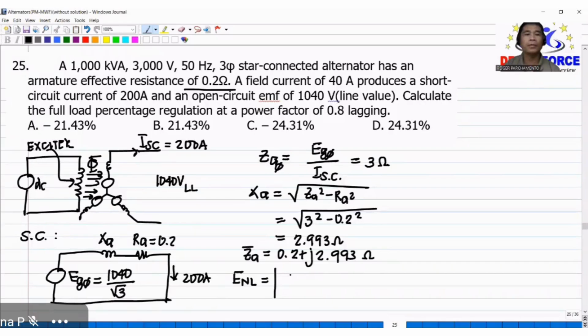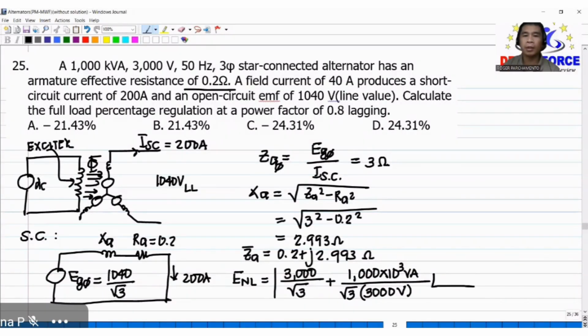E no load, magnitude of the line voltage 3000 volts. Gawin natin siyang per phase, so divided by square root of 3. Then plus yung line current. Line current is the output 1000 kVA, so times 10 to the 3 volt ampere all over square root of 3 times the line to line voltage is 3000. The angle would be a negative arc cosine 0.8. Then multiplied by the impedance 0.2 in rectangular, that will be 0.2 plus J2.993.